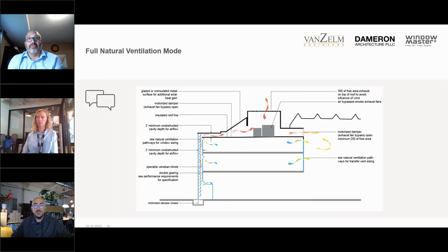We could use natural ventilation throughout the entire year. In the summer, we found it was only a handful of hours we'd be outside the ASHRAE thermal comfort range. So as part of the design, with some of the potential stakeholders, we ended up putting in a full mechanical ventilation system. But the way the sequences are written, we're letting that be second, on the back burner. Step one is to use natural ventilation as much as possible, and only if conditions inside get too much do we utilize mechanical. That was a definite transition in the train of thought of how an owner and stakeholder was thinking—normally it's just full air conditioning, go right ahead. But this was the complete opposite, a very nice paradigm shift.